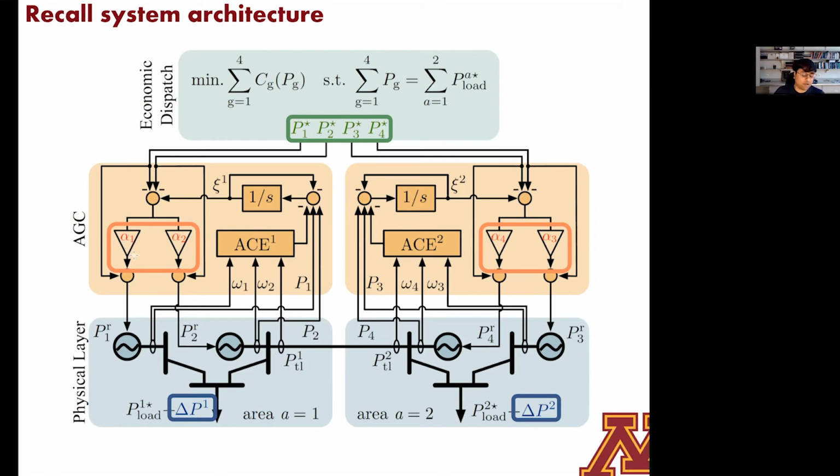And when you dig this out in a control theoretic framework, these end up being feed forward gains. So these quantities, alphas 1, 2, 3, and 4, are feed forward gains, and they are numbers between 0 and 1. If it's a number that's closer to 1, that tells you that you are going to be picking up a lot more of the net load and the losses that were not accounted for when you planned your trip. And if your number is somewhere close to 0, that means you're not going to be picking up as much of it. There's a whole history and a whole technical conversation that can be had about the way that you determine these. You can get a sense that these are important, and they absolutely are, but we won't get into that.